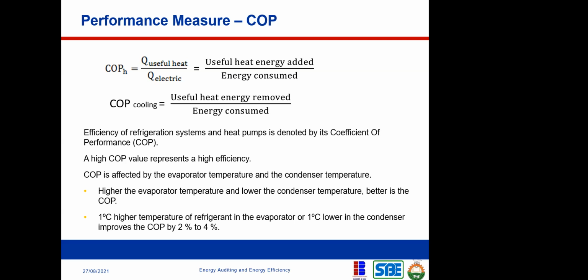The reason why it is said that the higher the evaporator temperature, the better for you, is that if you're running your air conditioning system at 17 degrees centigrade, you're going to consume a lot of energy. That's why you need to increase that temperature from 17 to maybe 22. So the higher your evaporator temperature, the better your COP. Then it also tells you that the lower your condenser temperature, that's the one outside, the better. You will notice that during cold weather your air conditioning system seems to be more effective, because the weather outside is cooler, so the efficiency of the air conditioning system improves. The lower the condenser temperature, the better your COP.